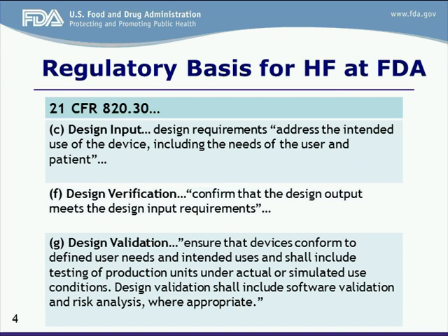So to get started, the regulatory basis for human factors. For human factors, there are basic tenets within design controls, 21 CFR 820.30. Design input is asking for the intended uses of the device, including the needs of the user and the patient. This can be identified and defined through human factors methods, and it's fundamental to the development of the project.